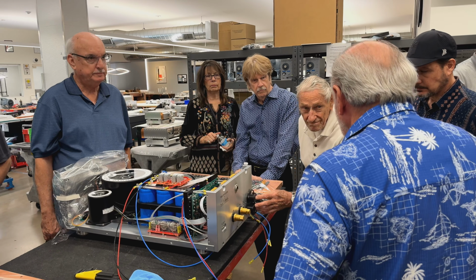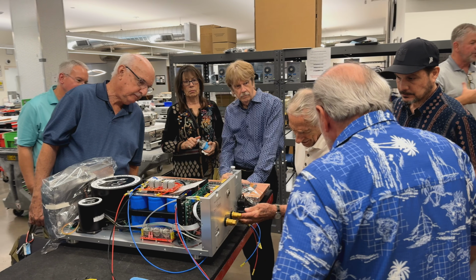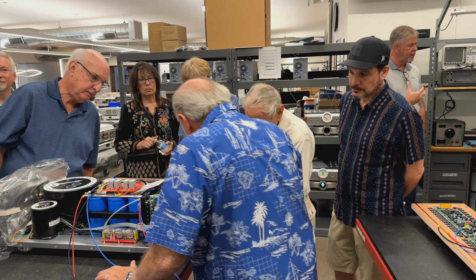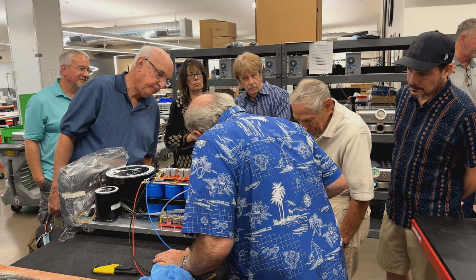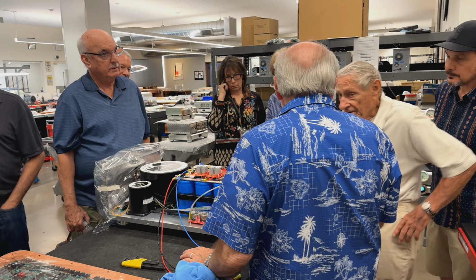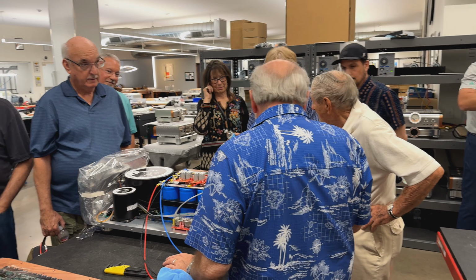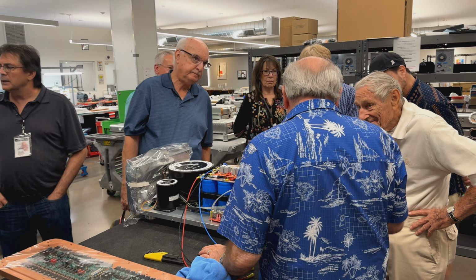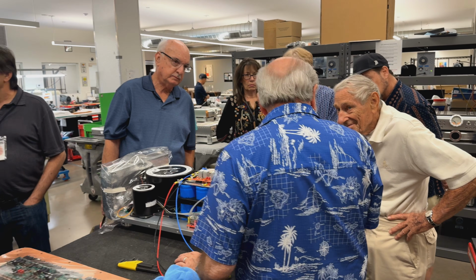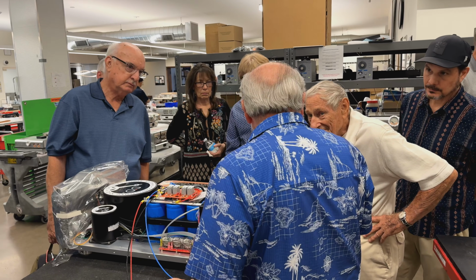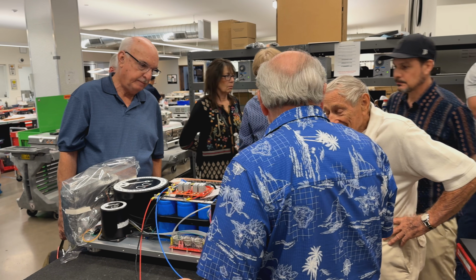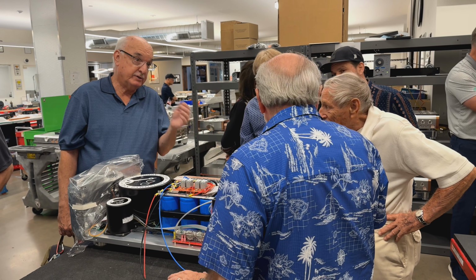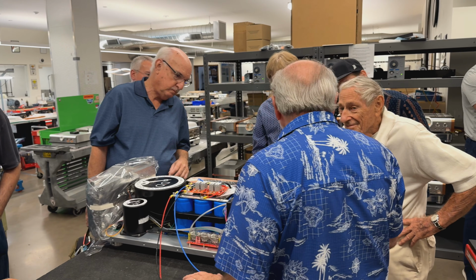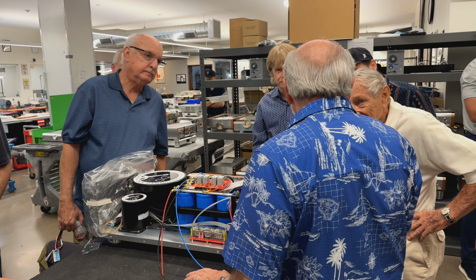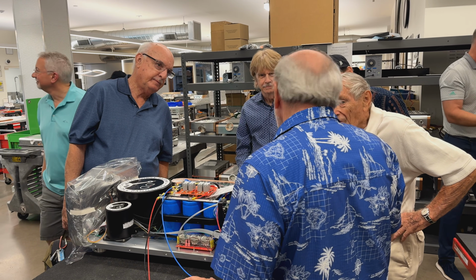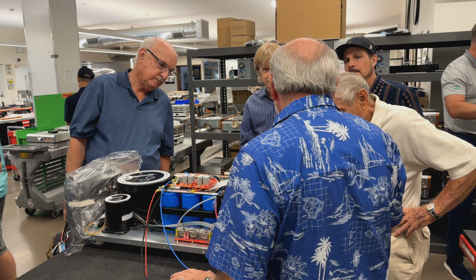It's a circuit breaker. Kind of small for that? Well, it can carry - it's 50 amps at 240 volts. You can go buy a breaker like that at Home Depot or Lowe's and it'll cost you about $25, but this one costs $150. Why is that? Because it's super fast and there's no leakage current - so when you turn it on, do you ever flip your breaker and hear it hum or buzz? This doesn't do that. This is a real breaker, the way they're supposed to be made.